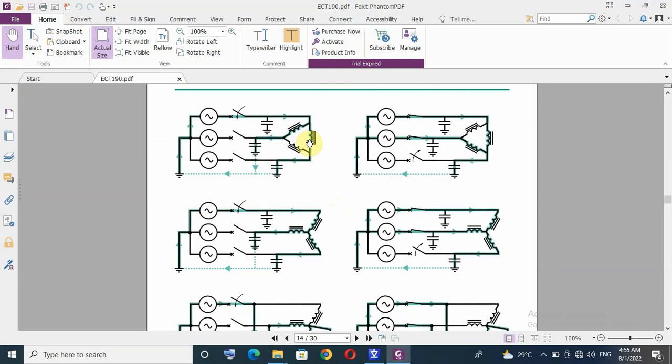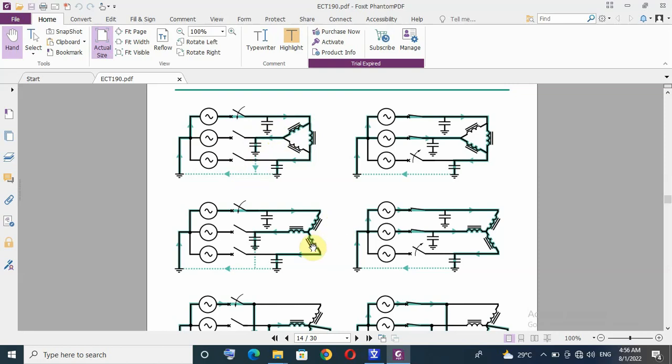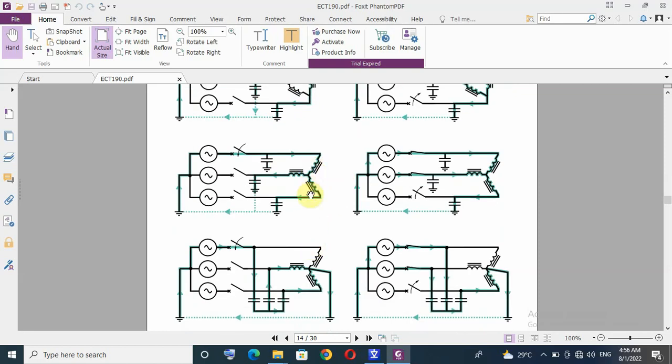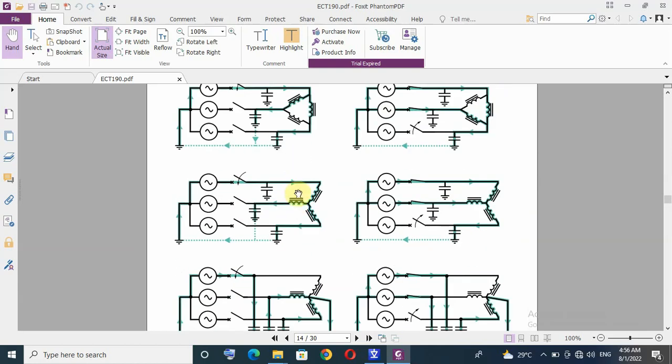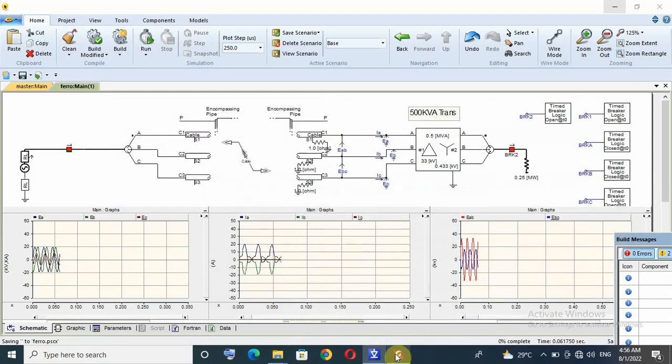Earthed cable with delta connected primary side and single phase operation and earthed system supply. Because here this winding connected in series with capacitor. That means XL of transformer and XCC of cable. This is sheath capacitance of cable from core to earth connected in series. Or star and earthed. And also it's possible with earthed star if we have core to core. That means this cable not earthed. So this three configuration for ferro resonance to have it also.